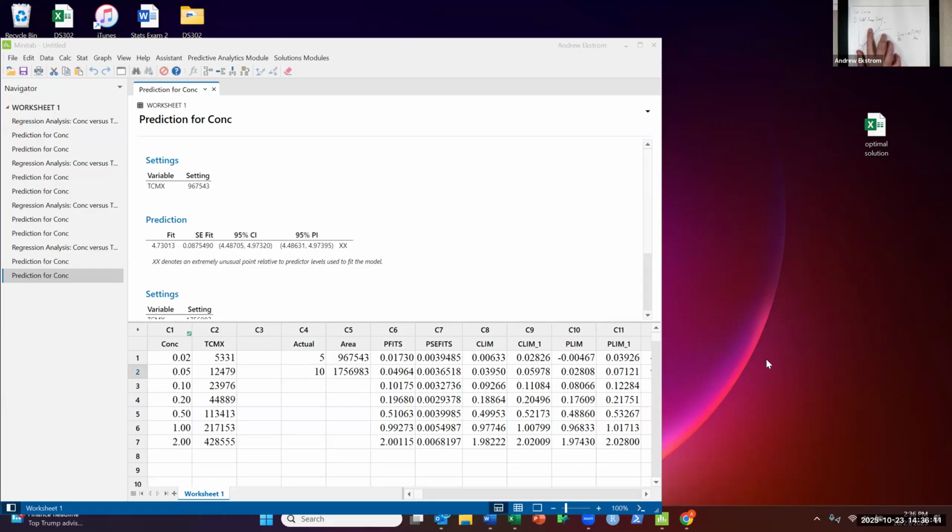our calibration curve is only valid within the range of the inputs that we have. If we force it to be this linear regression model, we find that it actually can't predict a bunch of the standards that we put in there accurately.